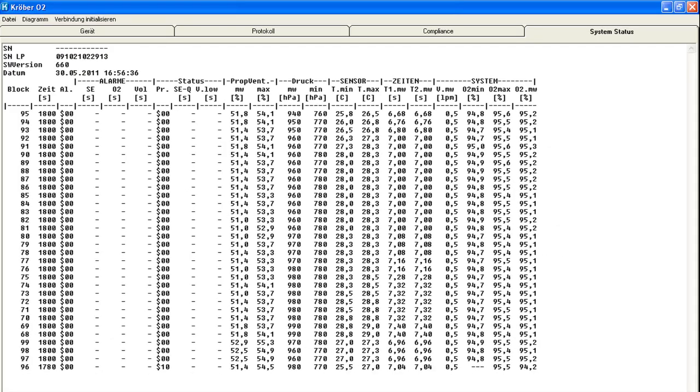An error-free report will appear as follows. There are no alarms present. The gas temperature is within an acceptable range. The cycle times of the two columns do not differ greatly from one another. The oxygen performance volume flow set is sufficient.